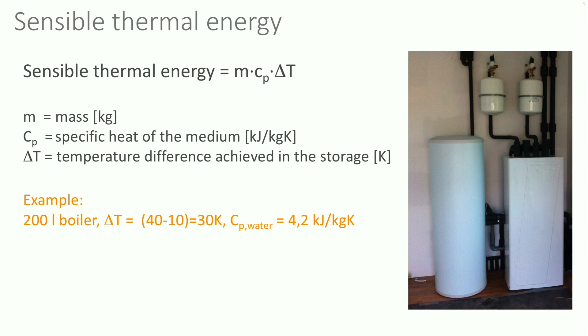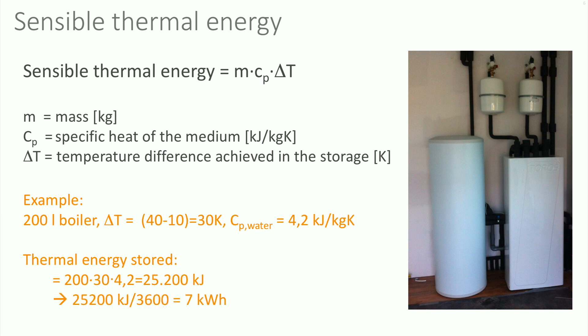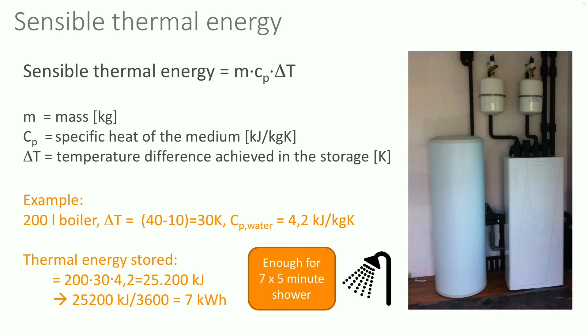The thermal energy stored is thus 200 times 4.2, which equals 25,200 kJ. If you divide this value by 3600, you will get the energy content in the unit kWh, resulting in a value of 7 kWh of thermal energy stored. This is enough for taking 7 showers of 5 minutes.